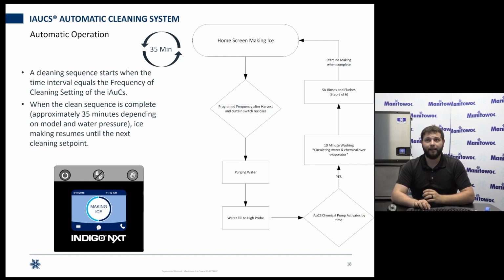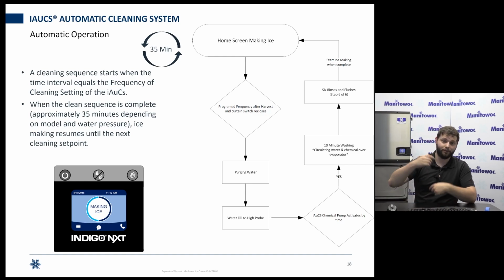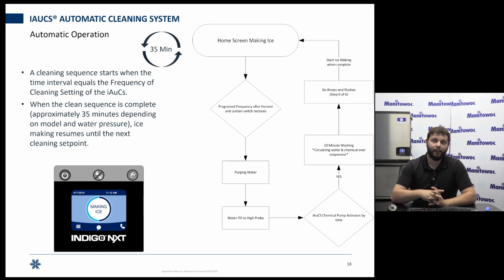After that, it'll do 6 rinses and flushes. It'll circulate and then flush that water, circulate again, flush the water, circulate again, flush the water. Once those 6 are done, it'll go back into the ice making sequence. So that's how the sequence of operations works for the iAuCS system.